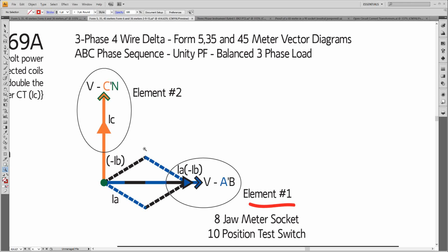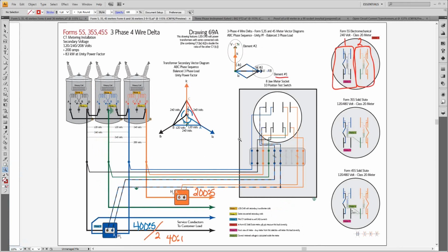And like I said, if we went down and actually got the numbers here, we could prove that if I added IA and minus IB together, I'd get 86% of them here at 240 volts. I would get full current here at 208 volts, which is 86% of that. So I get half of my torque on my meter here, the other half of my torque on my meter here, and so a nice application here. Even though it's not Blondel's, it works out pretty well how it's wired there. Somebody was smarter than me to figure out how to do that.